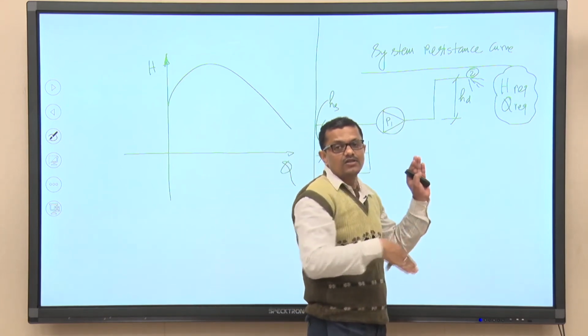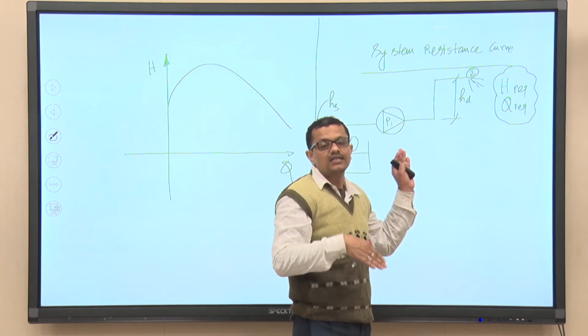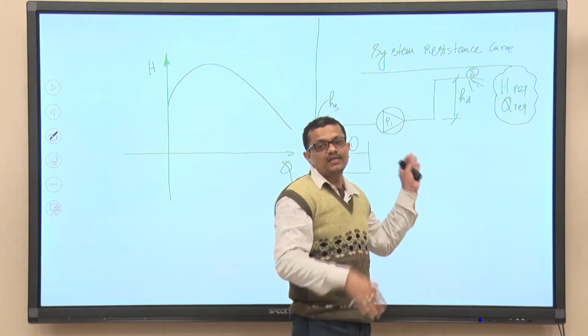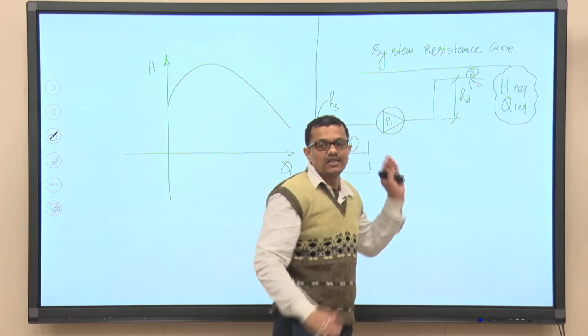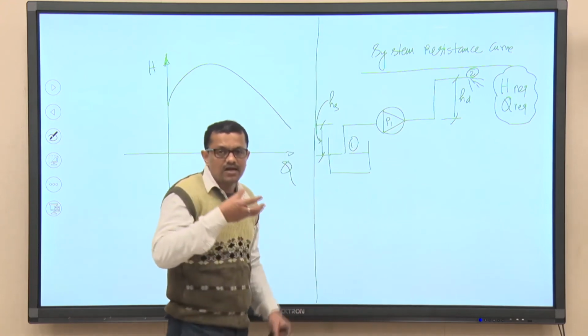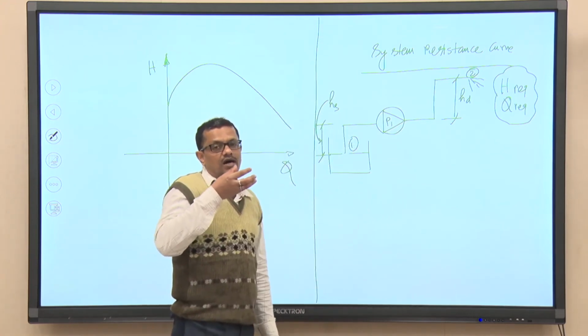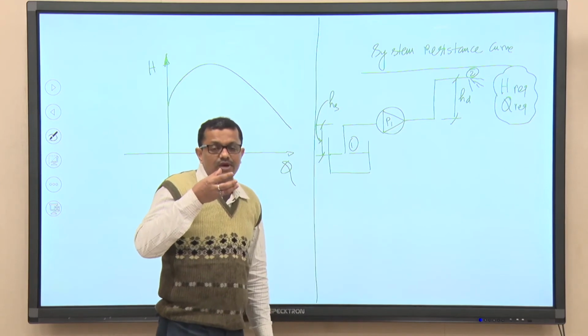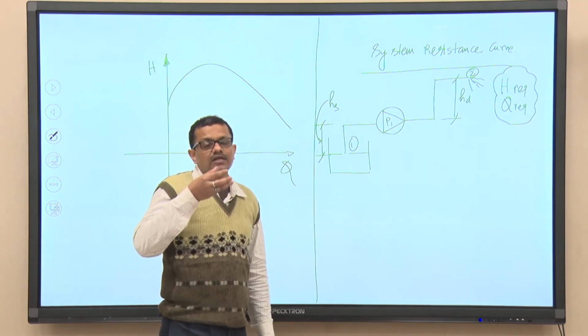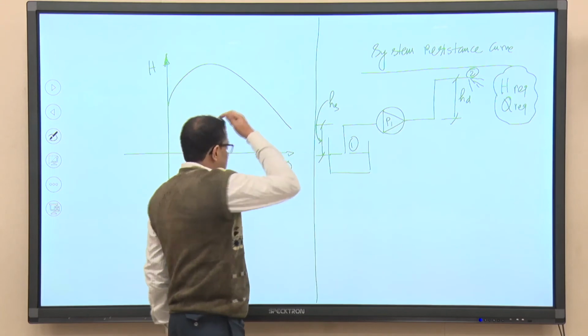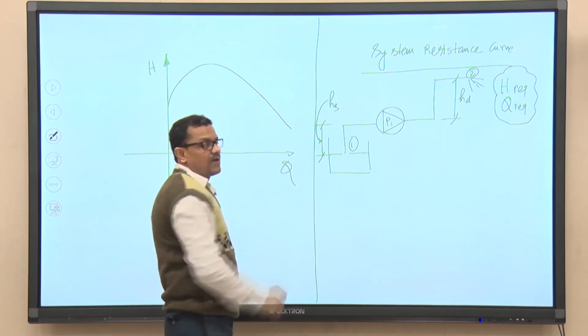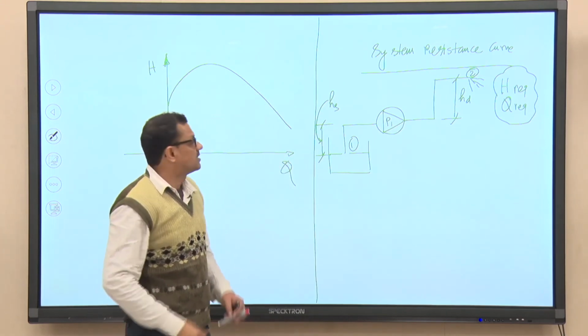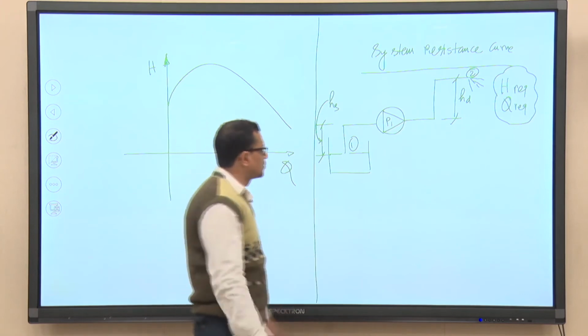So, again the most important part is that the design engineer designs this pumping system in such a way that the operating point is obtained, which is nothing but the point where the system resistance curve meets the pump's own characteristic curve, and that point is the operating point. We will see it soon.